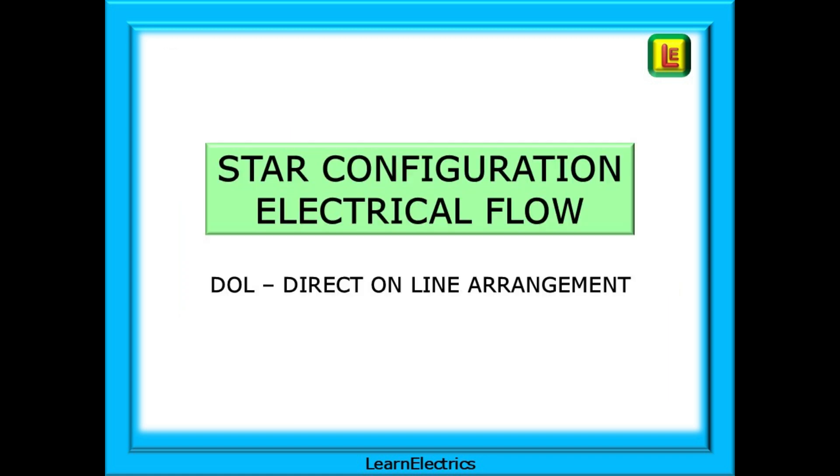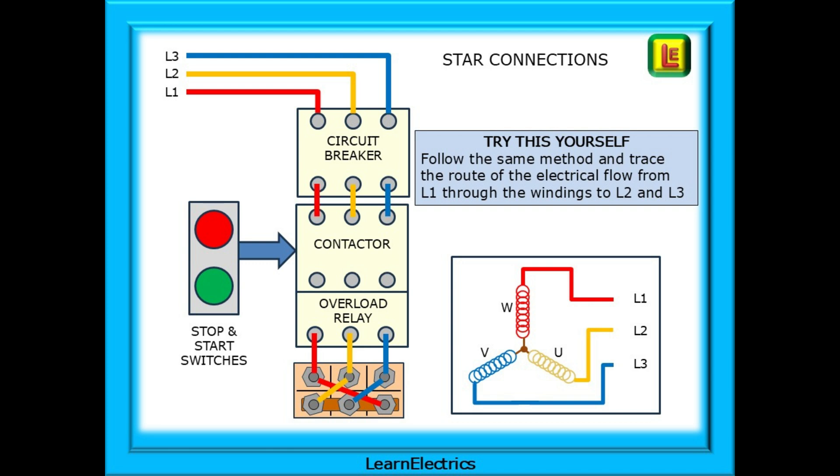How will a star configuration differ? This is still a direct on line or DOL arrangement. This is the same format for the circuit breaker, contactor, and overload relay. What will change is the layout of the brass strips. This time they connect U1 to V1 to W1. All the 1s are connected, and the power conductors are on the number 2 terminals as shown. Try to follow this electrical route yourself. Follow the same method and trace the route of the electrical flow from L1 through the windings to L2, and then follow the route from L1 to L3.